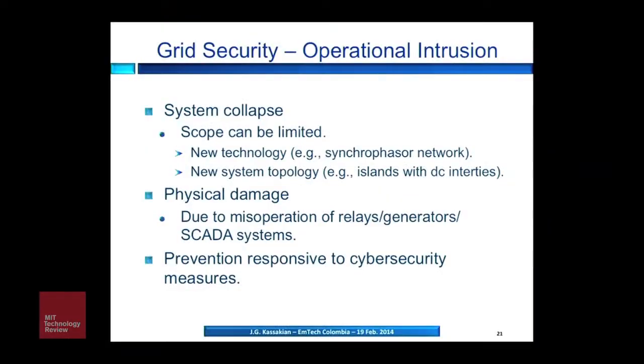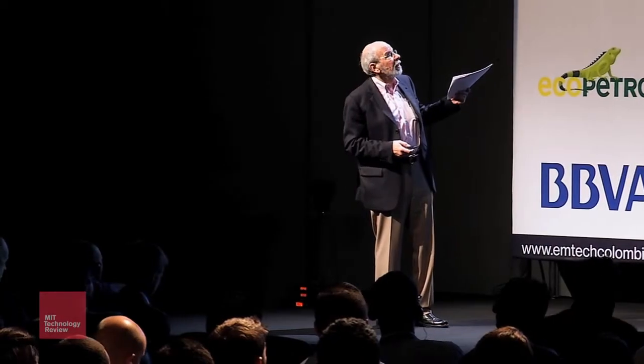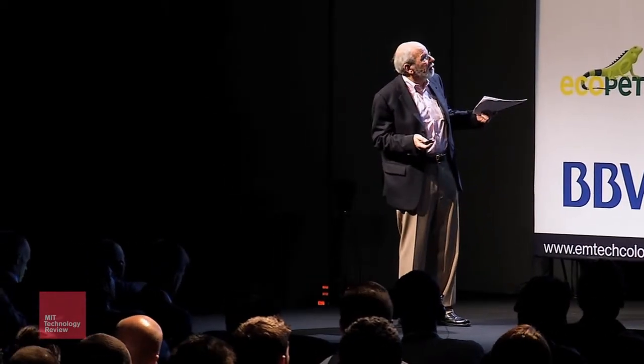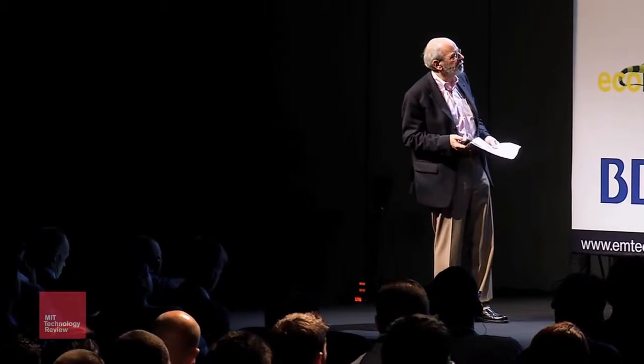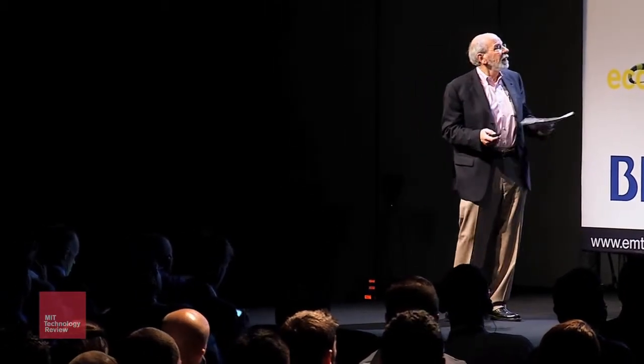There's operational intrusion—intrusion to the grid that creates a problem with how it's operated, calling for a breaker to open or close, or a generator to drop offline through a control system. This could create physical damage if the intrusion caused a generator to come online out of synchronism, and could cause a system to collapse.